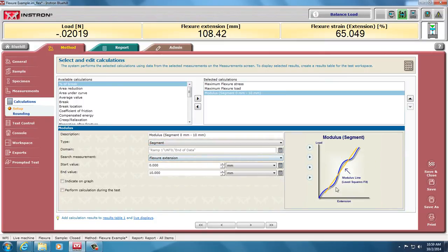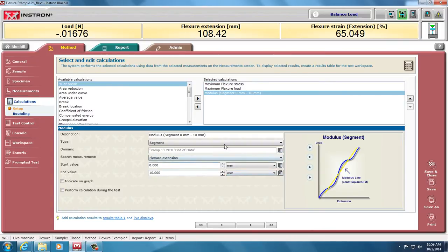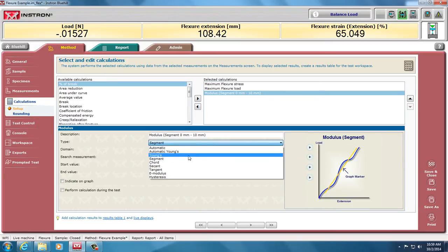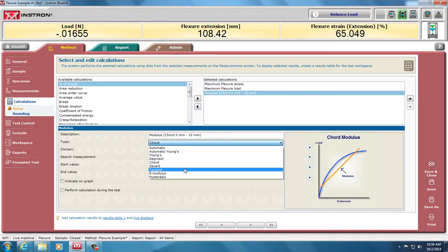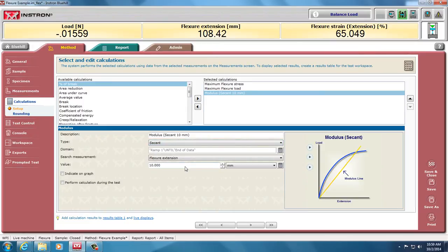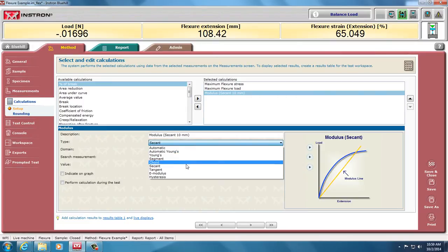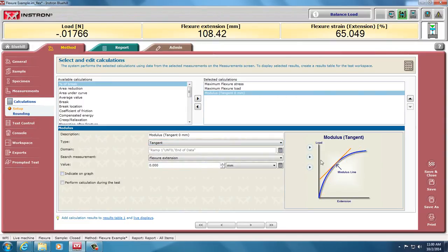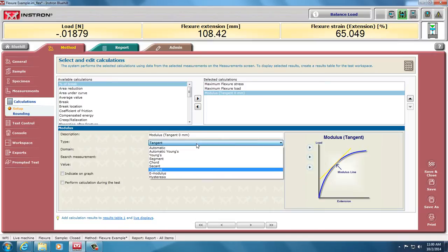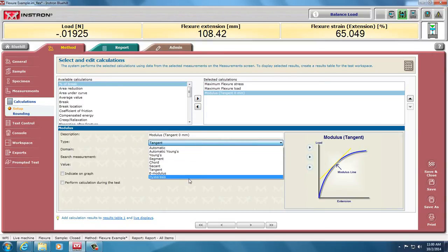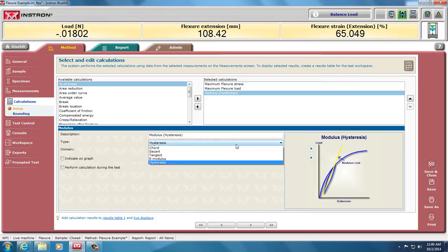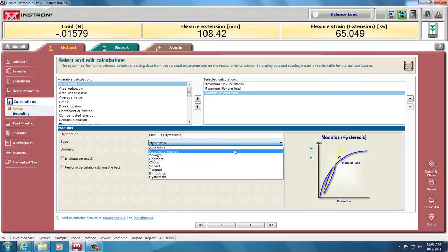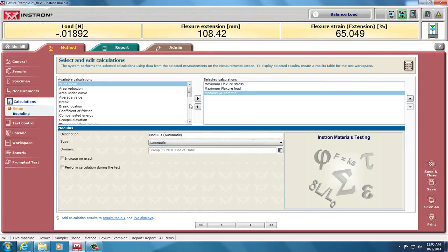You could have segment moduli, such as only look between 0 and 10 millimeters and give me the slope between there. You could also pick chord, secant, tangent. These are mathematical values that you should know about. And you can pick any of those. Even with hysteresis, it can take the modulus of the hysteresis. Halfway through the hysteresis is not in the center of the curve. But I'll go back to doing just automatic for this.